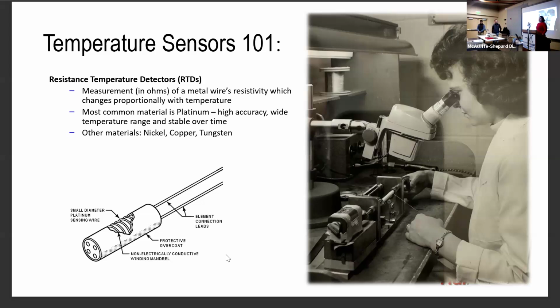But there are other materials that have always been used for RTDs as well. Some of them are nickel, also copper, and sometimes tungsten for very high temperature measurements, because platinum tops out at around 600 something Celsius. But in any case, this is a very, very small diameter platinum wire, and it was RDF's innovation to create some of these jigs and fixtures, which enabled the manufacture of these sensors in Hudson. You might be able to make out a very thin wire there.